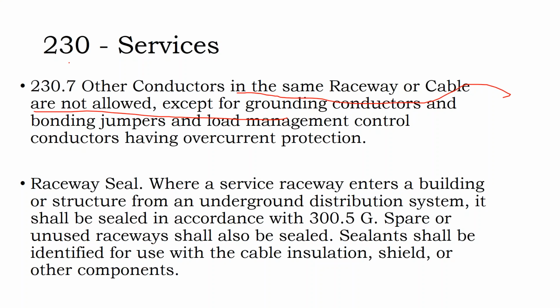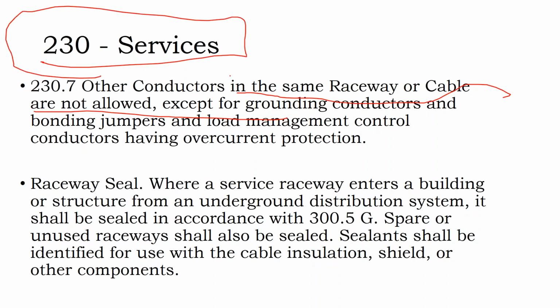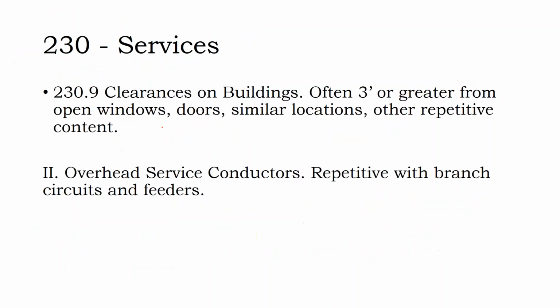But we also see that reflected early on in 230 services, where for our service entrance conductors, for our supply, other conductors are not allowed in the same raceway or cable except for grounding conductors and bonding conductors and other conductors having to do with on-site energy management. And they're not just saying supply, it says load management control. So maybe that involves not just decreasing your energy usage, but increasing your energy usage in a cost-effective manner. You know, if you want to install a Bitcoin miner right next to your solar array, you could call that a load management control device and use the same conductors. And then we see our raceway seal requirement that we already talked about yesterday.